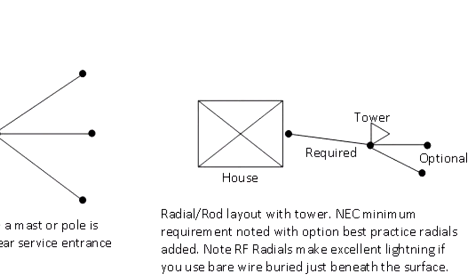Whereas the ground electrode bonding jumpers or radials, you can take them quite a bit deeper, but if you're going to run RF radials, you want them right near the surface so the RF doesn't have to penetrate dirt, like this dirt can't conduct electricity or earth very well.